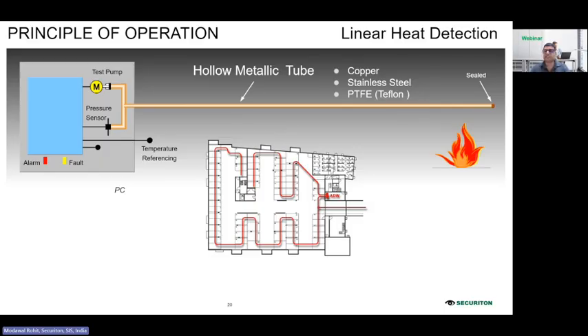So if the tube reaches a preset temperature, like 90 degrees, 105 degrees, 120 degrees, or 60 degrees, 70 degrees, then when it reaches that preset temperature, the detector also triggers an alarm. So this is what these two technologies do, this ensures detection even in the case of slow developing fires. So both the possibilities are there, or there is a combination also you can use.